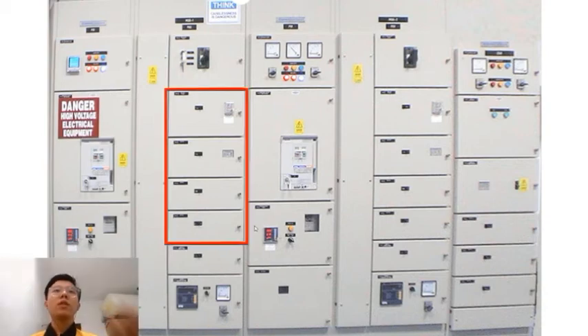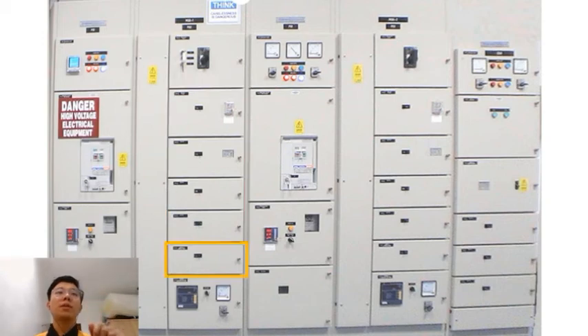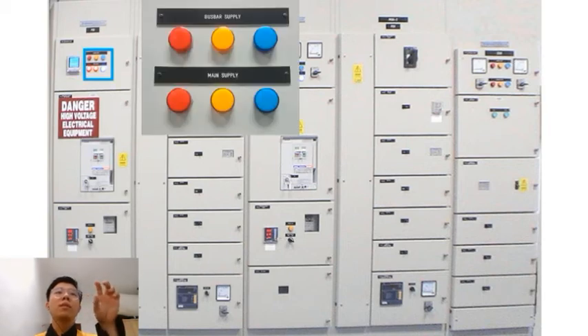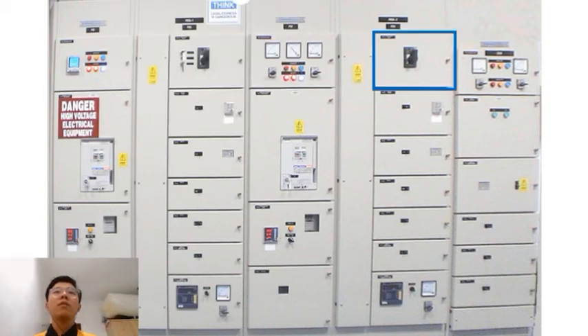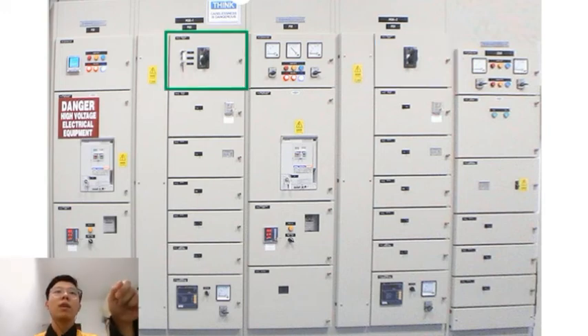First, we need to turn off the MCCBs at the MSB1 one by one. After we turn them off, we turn off the power factor capacitor and we check the current status. After we check the current status, we turn on the isolator and now we will check the bus bar supply indicator light, and it should not have any lighting.